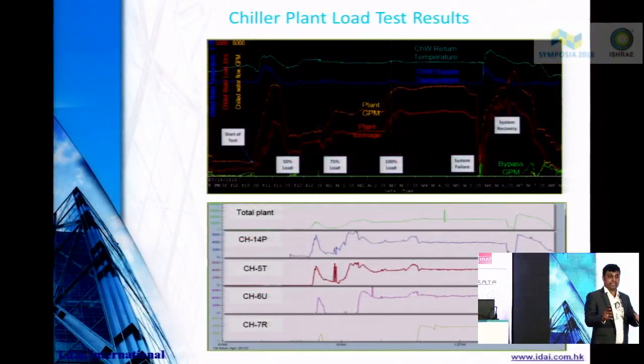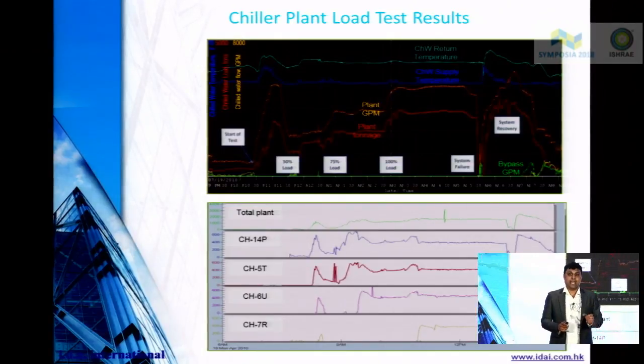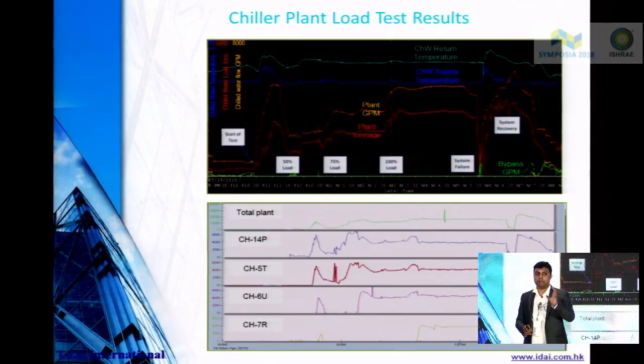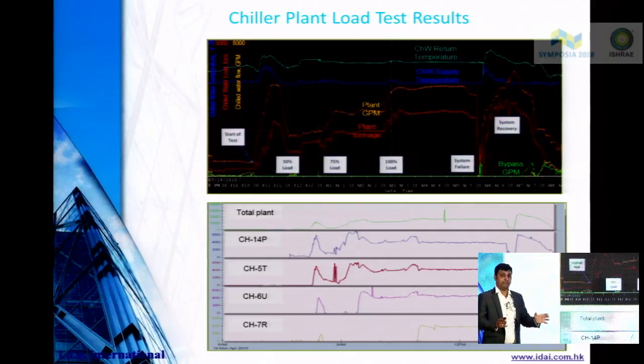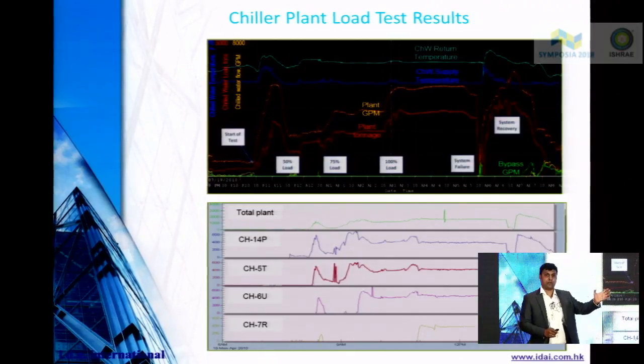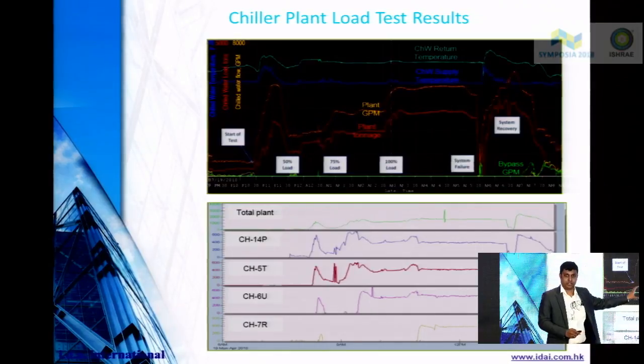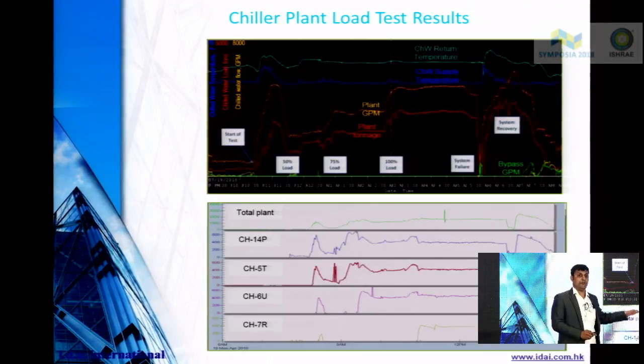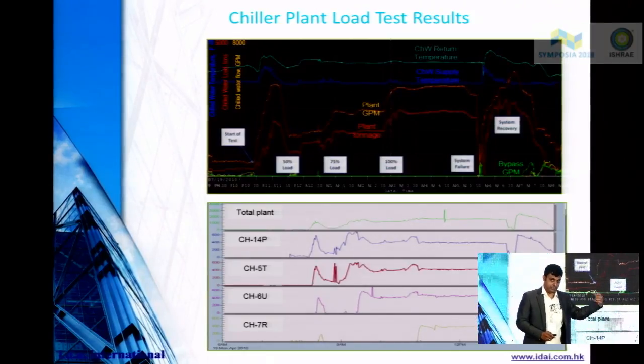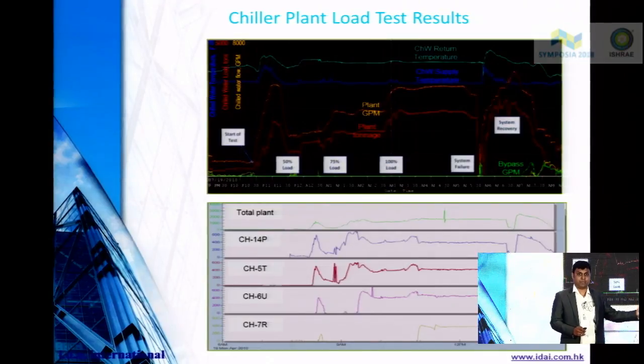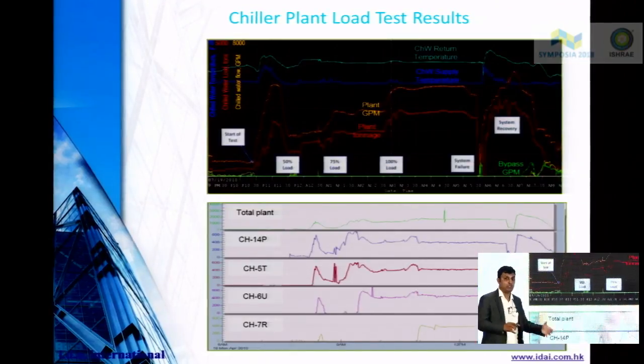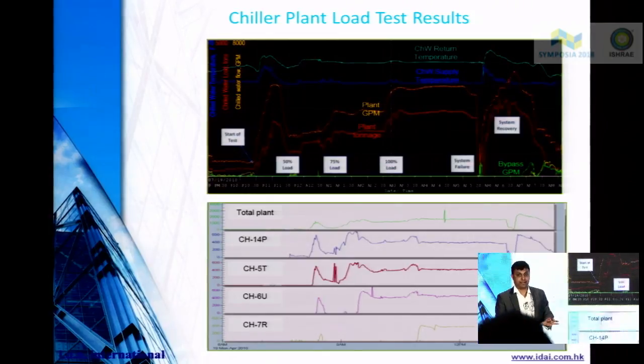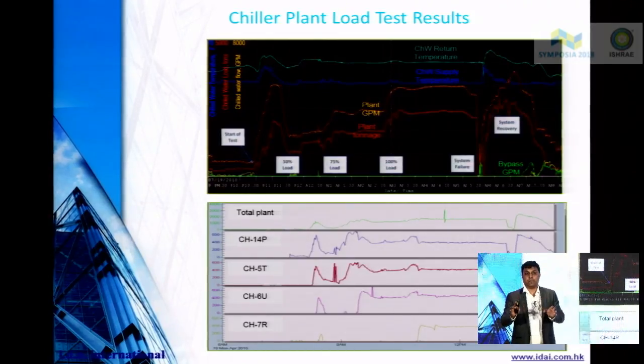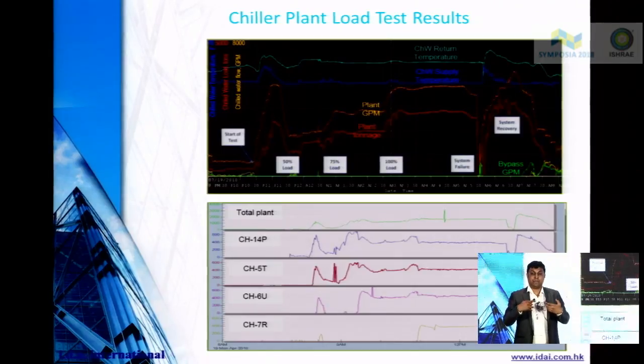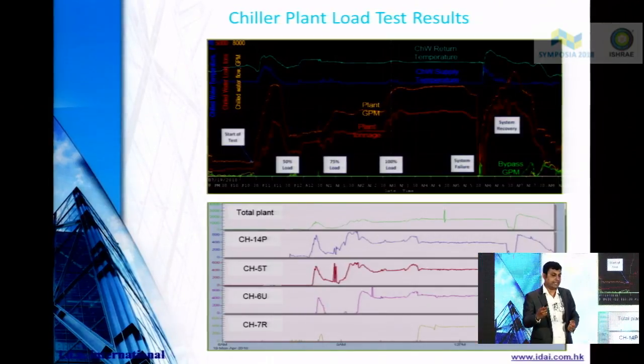Again, when you're doing the heat load test, it is very important to verify the central chiller plant. How do we verify? When you're loading the data hall from 25% to 100% load, you have to see the behavior of the chillers and see how the chilled water temperature behaves. Is it stable? Is it rising? Was there a temperature more than your acceptable criteria? You have to verify that. You have to see the chiller loading. You have to study the chiller plant and then decide whether it is able to take the load and behave the way your design intentions are.